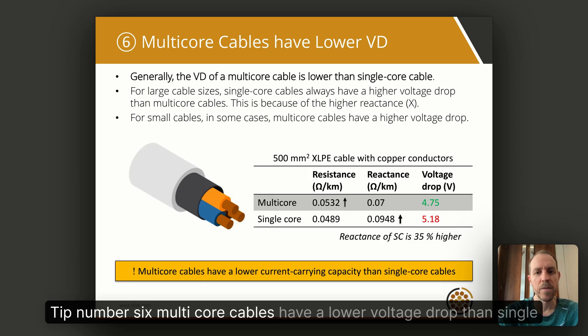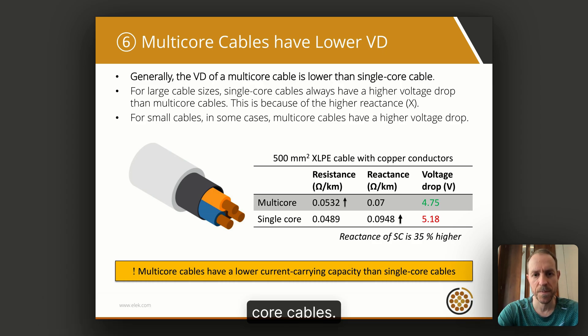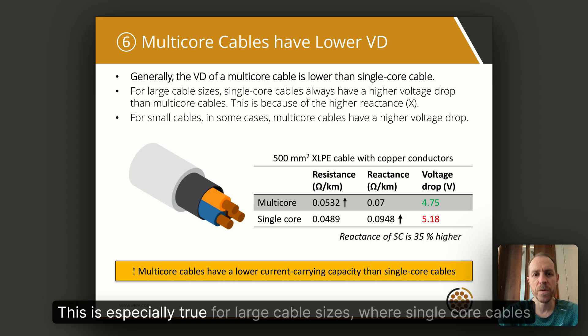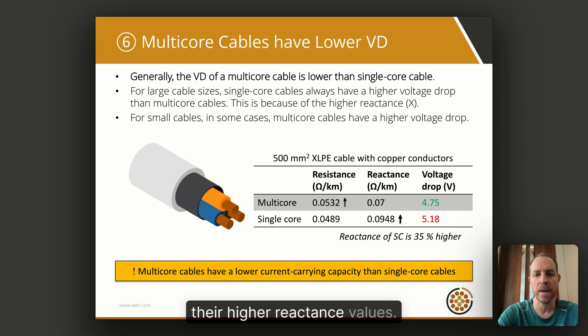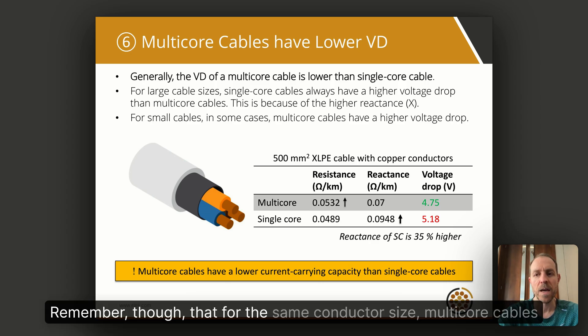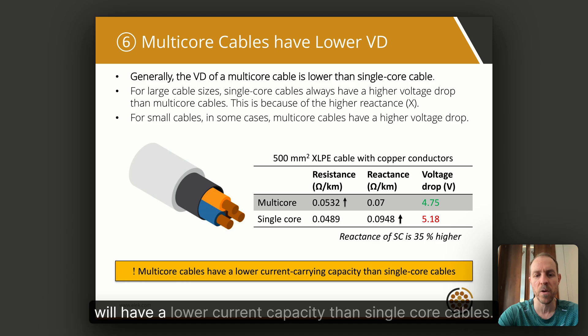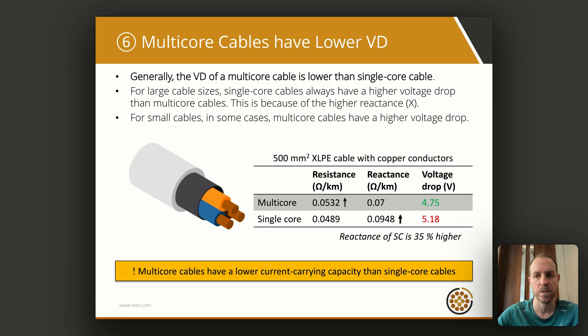Tip number six: multi-core cables have a lower voltage drop than single-core cables. This is especially true for large cable sizes, where single-core cables will always have a higher voltage drop than multi-core cables because of their higher reactance values. Remember though that for the same conductor size, multi-core cables will have a lower current capacity than single-core cables.